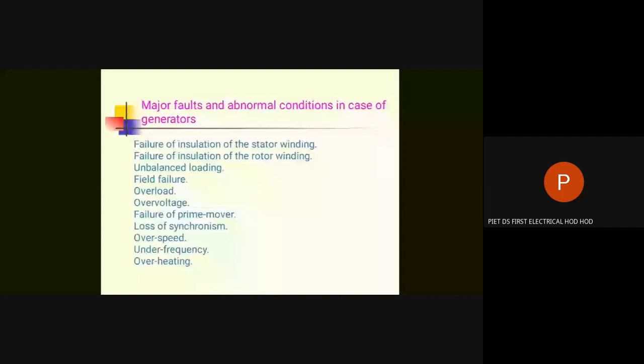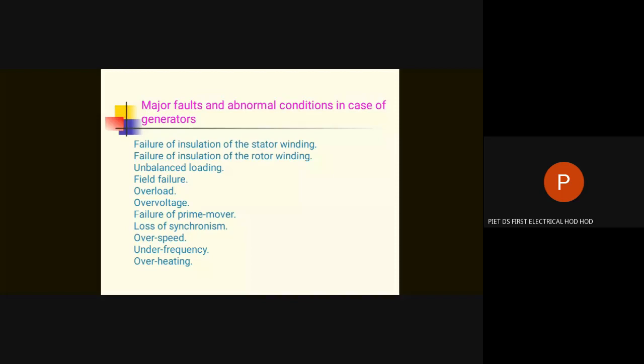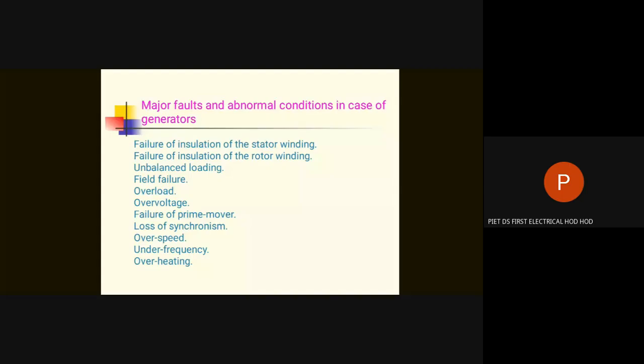With reference to tripping of a generator, usually the protective scheme is divided into three different parts. Before we come to that, let us have a look at the major faults and abnormal conditions in case of generators. You are seeing the slide in front of you.